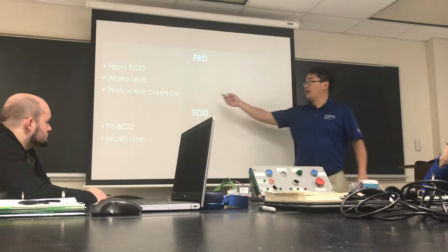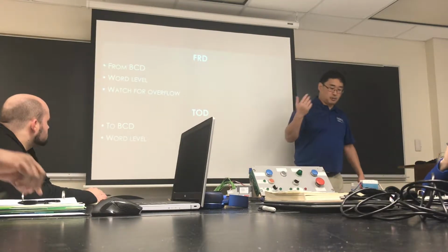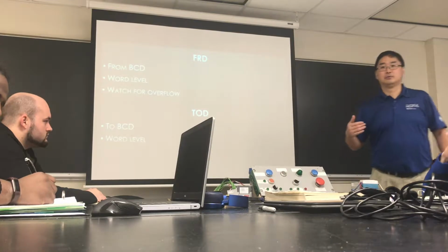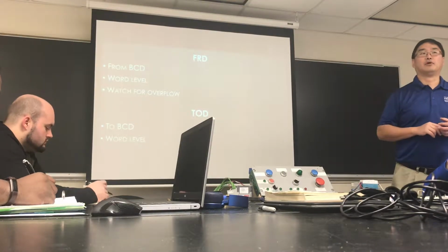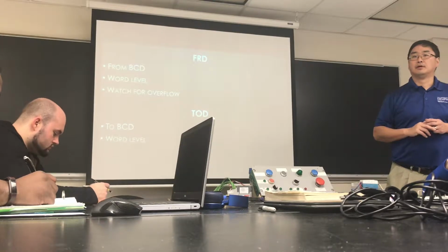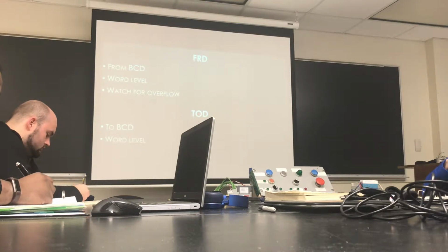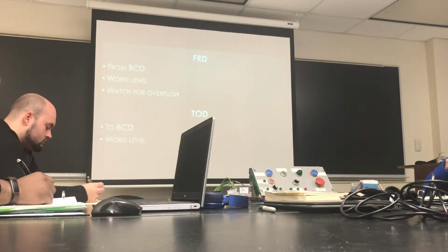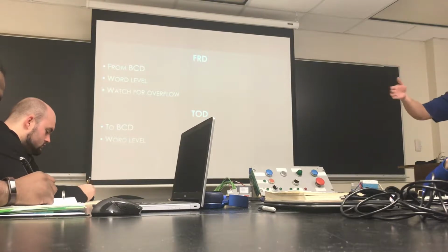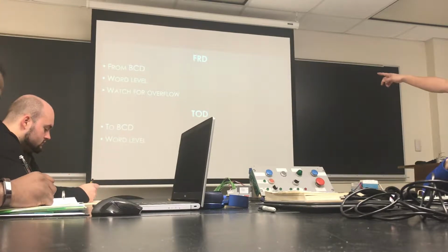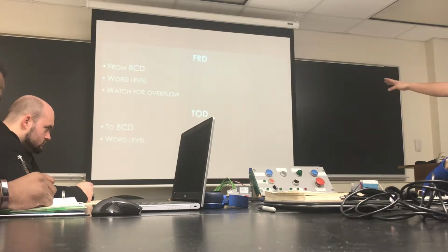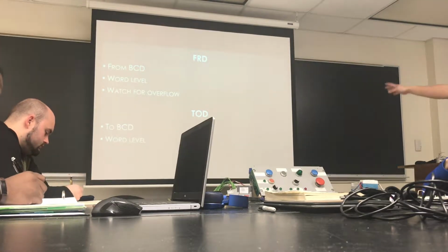It is the word level, and this is the one you have to be careful of. If I do a mask move out of my input table, I can overflow my decimal number. 16-bit decimal is 65535. I just remember that sequence because I deal with it all the time for something else. That's bigger than a standard normal integer in Micrologics. You have to use something called a long.